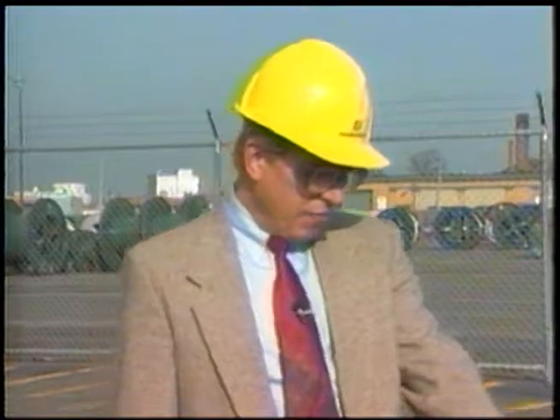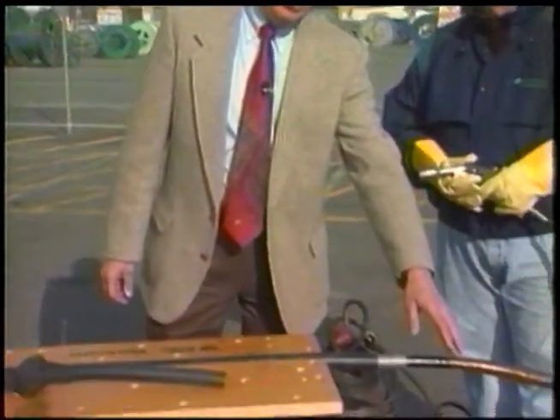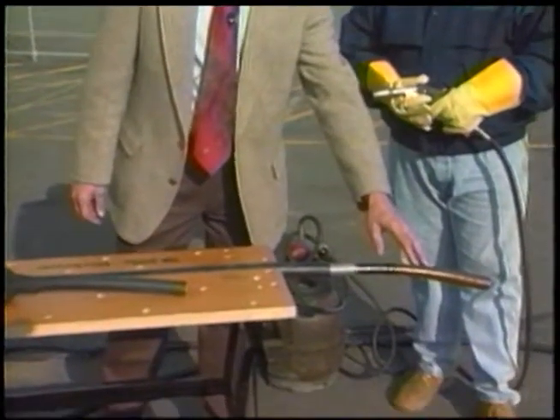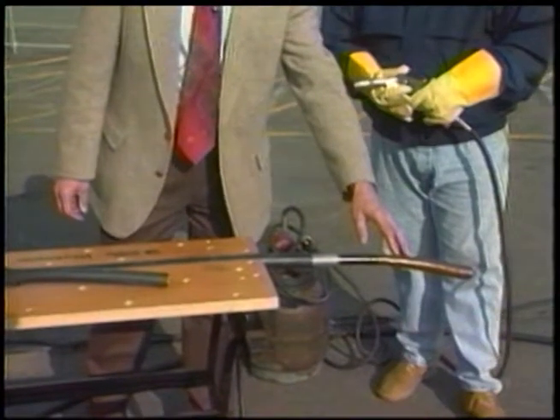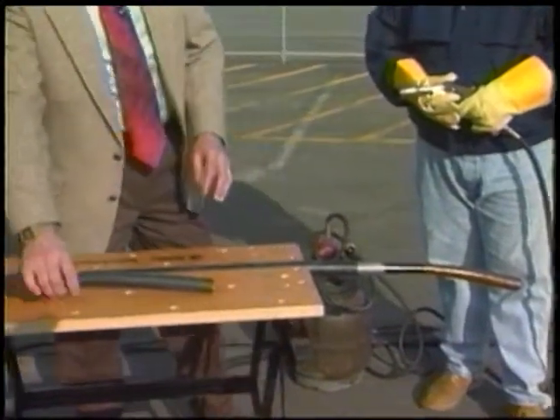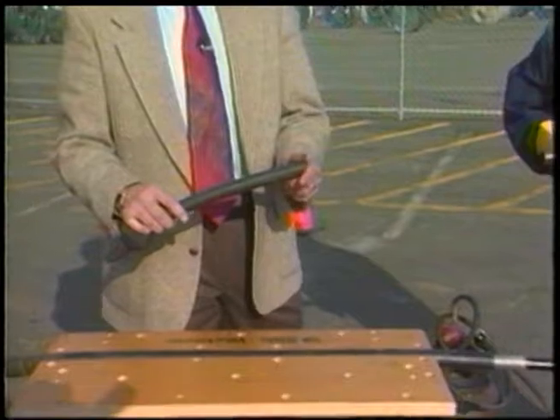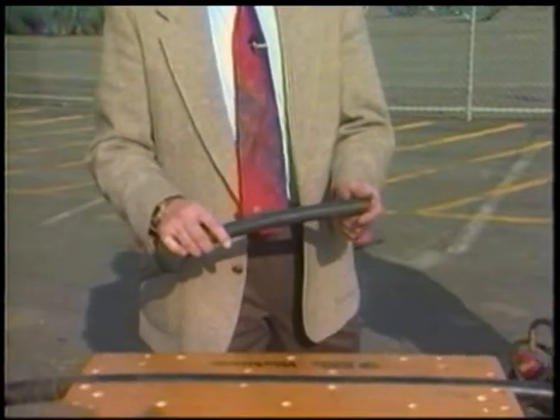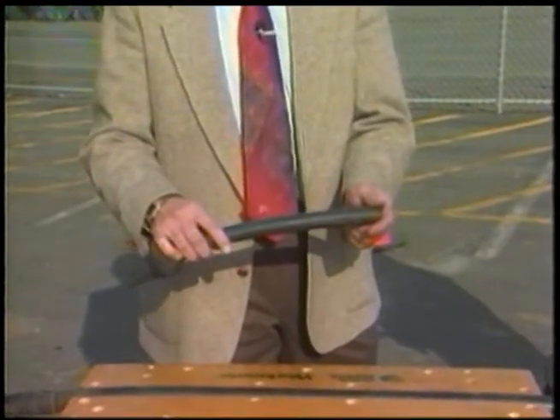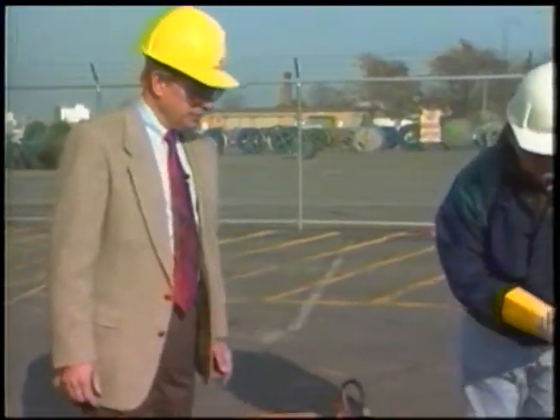This is the first demonstration. The first cable we have here is a paper and lead cable. These papers are saturated with oil, and you're going to see how it burns readily. The second cable you see here is a fire-resistant cable, and when fire goes to it, it wants to go out right away. Kurt, we're ready to set the cable on fire.